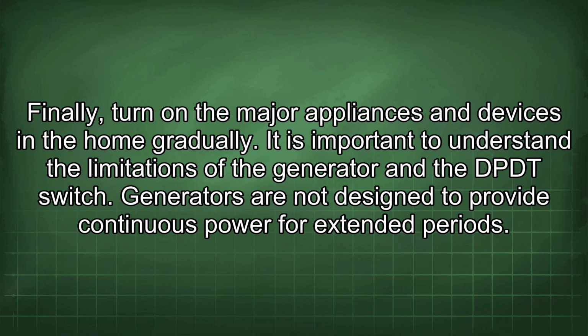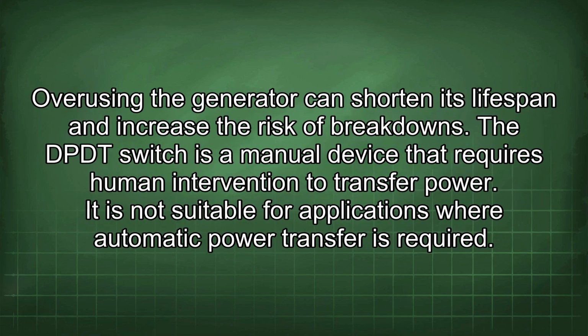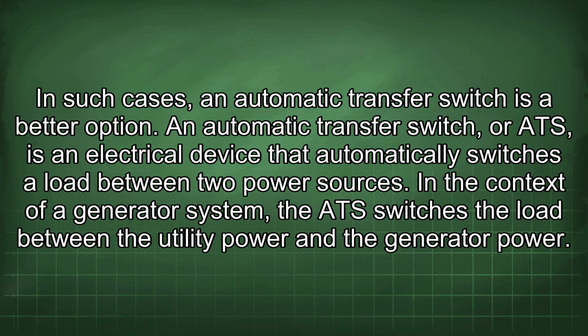It is important to understand the limitations of the generator and the DP-DT switch. Generators are not designed to provide continuous power for extended periods. Overusing the generator can shorten its lifespan and increase the risk of breakdowns. The DP-DT switch is a manual device that requires human intervention to transfer power. It is not suitable for applications where automatic power transfer is required. In such cases, an automatic transfer switch is a better option.